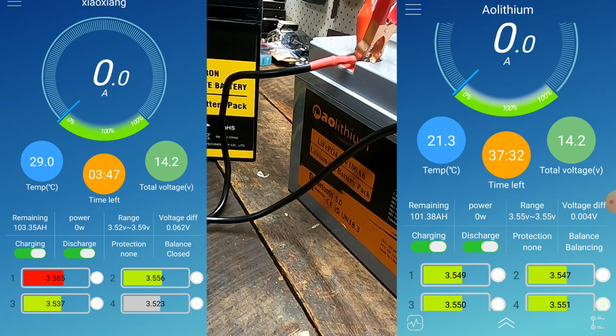You can see 4 millivolt in the AOLithium - that was after one full charge with this battery and charge balance turned off. Before, we had like 150, 151 millivolt deviation, and even this 70-80 milliamp balancing was enough, within an hour to 1.5 hours, to balance this pack if you turn off charge balance.